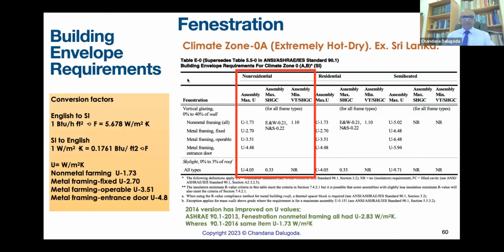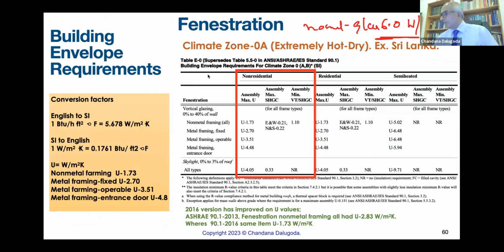Now fenestration, that is windows, glasses. Remember I told you 6 watt per square meter Kelvin for normal glass. But we'll have to drop it to 1.73. That is for non-metal framing, that is wood, or metal framing 2.7, metal framing operable 3.51. Usually we are at 6 watt per square meter Kelvin, which should be dropped to 3.5. So that is what we should be doing. You can't use normal glasses.